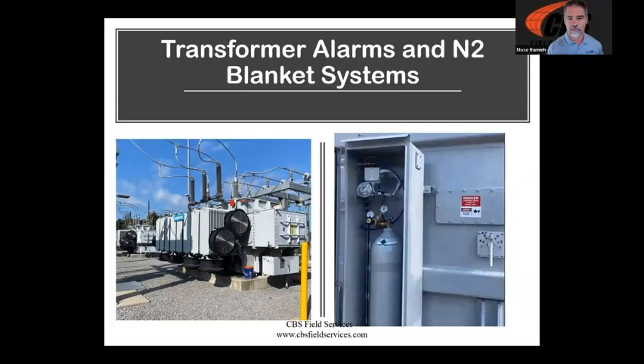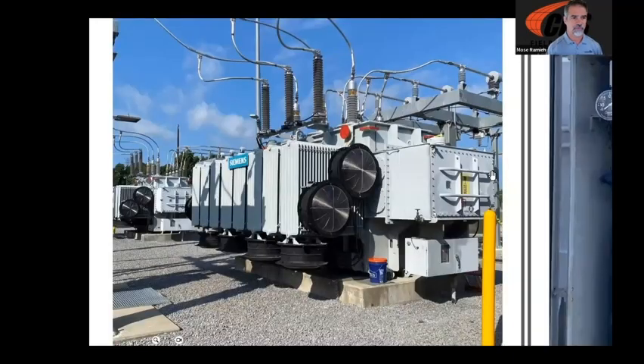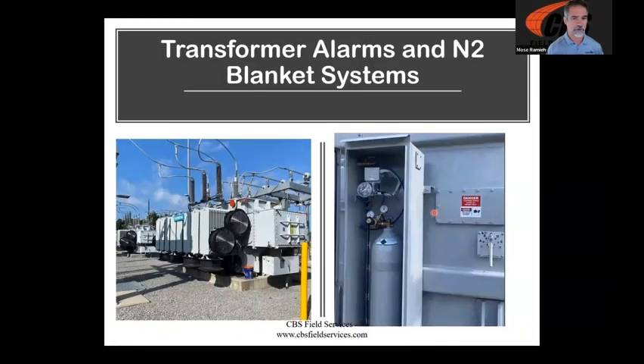We had a client that was not maintaining their transformer nitrogen system, and it was particularly this load tap changer right here. If I get my pointer in the right place, load tap changer. They ran their nitrogen bottle down to zero, and that allowed moisture to work its way into the transformer tank. The reason I bring that up is that moisture is bad inside of our transformer equipment, but in particular, what was the cost?